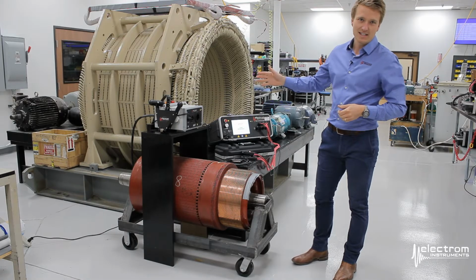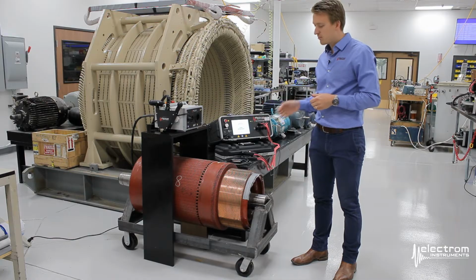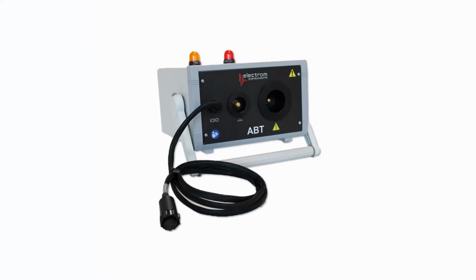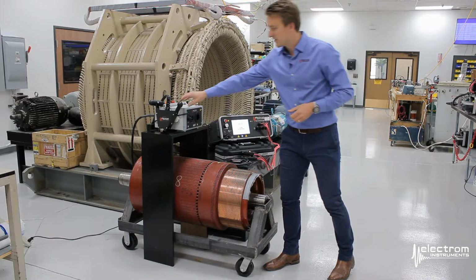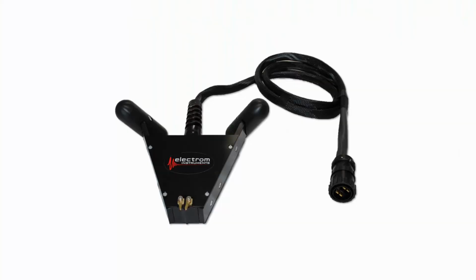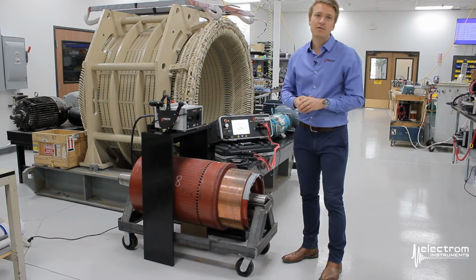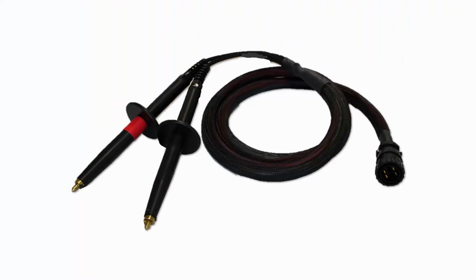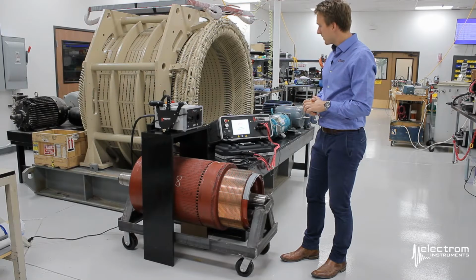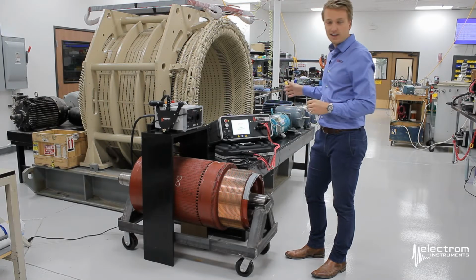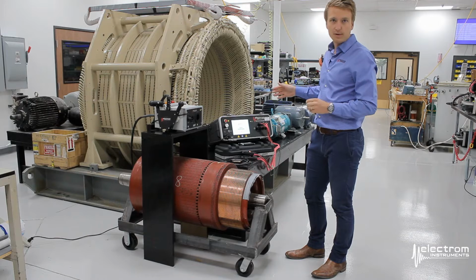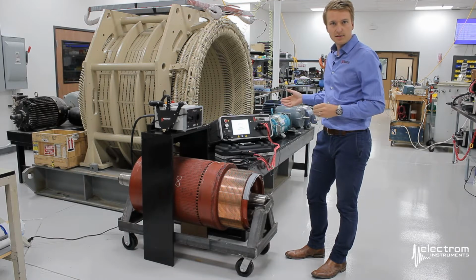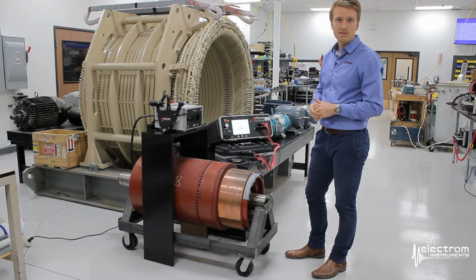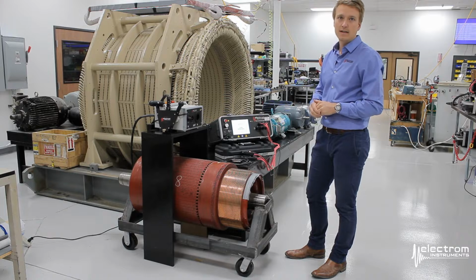The ABT is used for surge testing bar-to-bar on DC armatures. It comes with a BBP as the standard accessory or probe set, and we also have an additional or optional probe set called an ASP. The ABT is commonly used with an iTIG 2, 3, or a 4, preferably a 12 kV or 15 kV, but in many cases a 6 kV tester will also be sufficient.